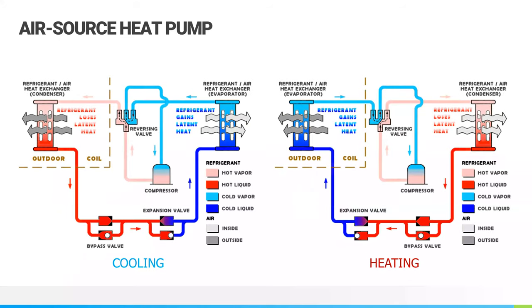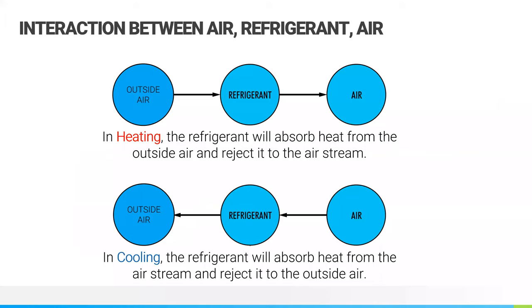So you've got different kinds of heat pumps. There are air source heat pumps, where you're transferring energy from one indoor source to the outdoor source. It really depends on whether you're in heating or cooling mode, whether you're rejecting heat outside or taking heat from the outside. Breaking that down, you've got your outside air interacting with the refrigerant loop, interacting with your inside air. In heating, your refrigerant's absorbing the heat from the outside air and rejecting it to the inside. And then in cooling, you're just reversing that cycle, absorbing heat from the airstream indoors and rejecting it to the outside.